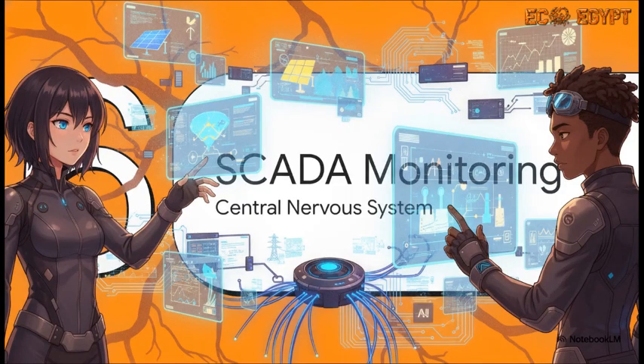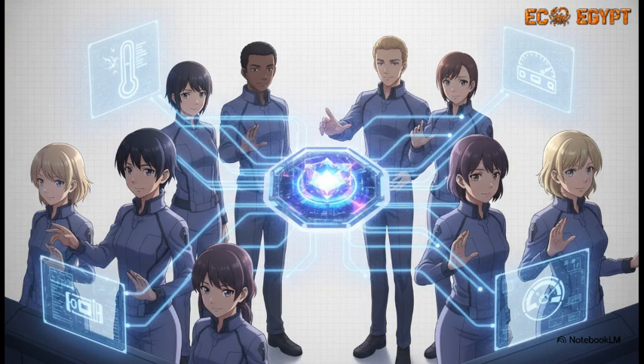Which leads us to our final section, Section 6, SCADA, Monitoring and Control. SCADA, which stands for Supervisory Control and Data Acquisition, is basically the central nervous system of the plant. It is constantly reading sensory inputs from everywhere. Using specialized communication cables running RS-485 daisy chains and Modbus protocols, it is pulling in real-time data nonstop. It instantly flags operators if an RMU trips a fault, or say if the SF6 insulating gas pressure drops. It's actively watching the transformers for overheating by monitoring the oil and winding temperature indicators. It tracks literally every power meter and tripped low voltage breaker. It just gives operators total 24/7 situational awareness.